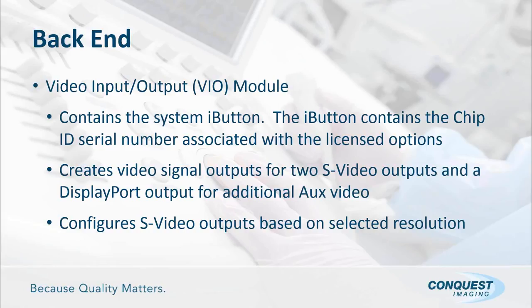Then we move on to the video input-output module. Again, if you're in back of the system facing the E module and looking inside it, these boards, the input-output boards, are located on the right-hand side of the module. So an important part of this is if you feel like your video input-output module is damaged or needs to be replaced, be aware that it contains the iButton, which is a chip. It looks a lot like a battery, and it has the ID of the system, the serial number, and it's associated with the license options that are installed on it. If you replace this video input-output module and don't take the chip off the old and put it on the new, your system will be unable to work as an ultrasound.